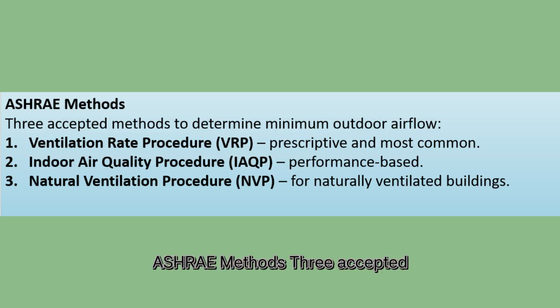ASHRAE methods. There are 3 accepted methods to determine minimum outdoor airflow. Ventilation rate procedure, VRP, prescriptive and most common. Indoor air quality procedure, IAQP, performance-based. Natural ventilation procedure, NVP, for naturally ventilated buildings. Most WSHP applications use VRP or IAQP, especially in humid climates.